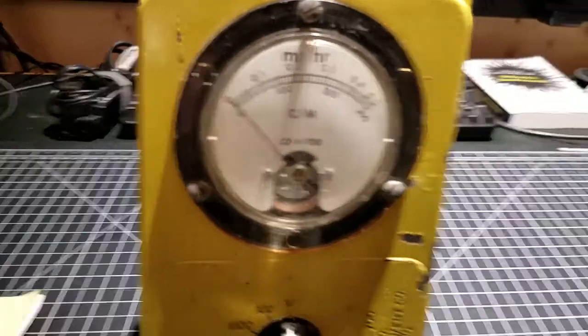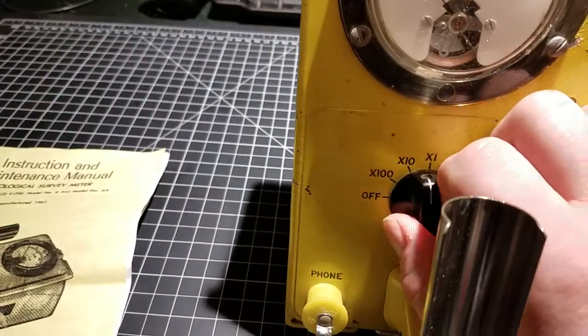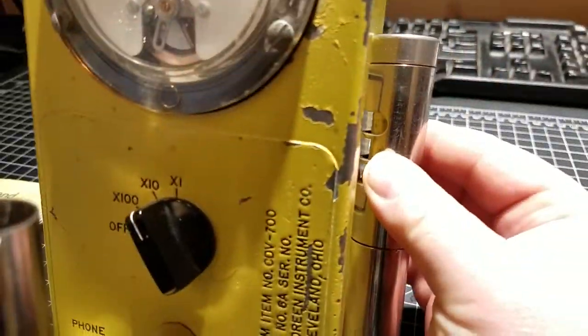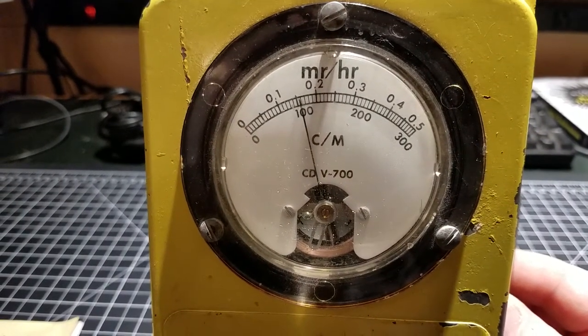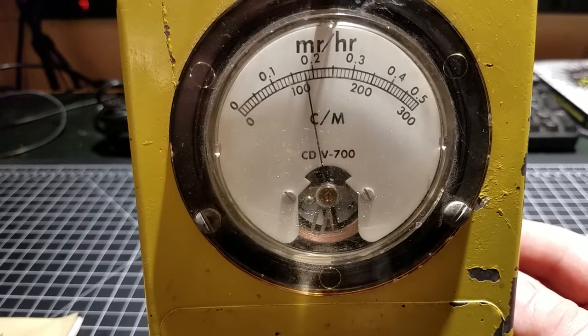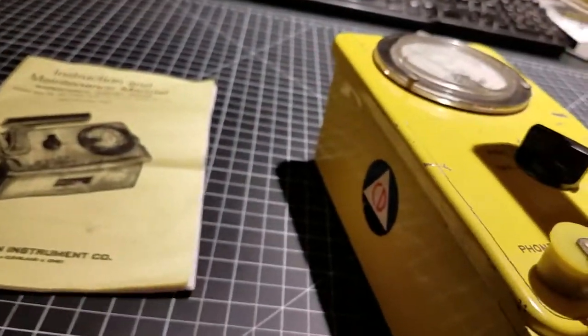You can see the meter face deflecting a little here. According to the manual, the way you're supposed to verify calibration in terms of counts per minute is to put it on the times-1 scale, open the check source window, and place it against the check source. We should read between 1.5 and 2.5 milliroentgens per hour to know that it's essentially calibrated. As you can see, it's calibrated and working — pretty close to 2 right on the line, and if you leave it there long enough it basically balances out at 2.